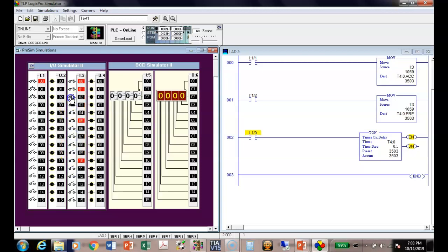And what's the maximum I could put into that? Let's see if RSLogix 500, if the simulation lets me do that. This guy, he does a real good job, but sometimes he lets us get by with things. So literally, I should not be able to load this number in there. And why is that? Because I got bit 15 set to a 1, which automatically makes it a negative number, right?